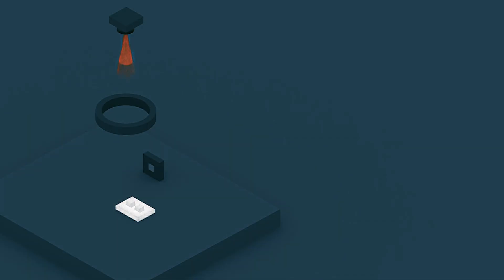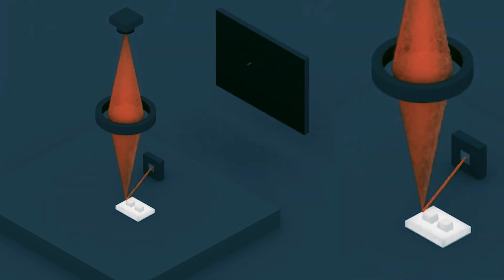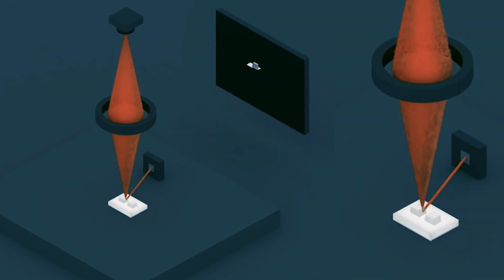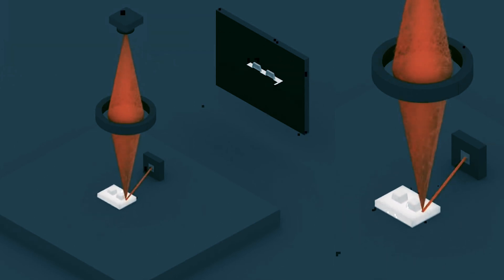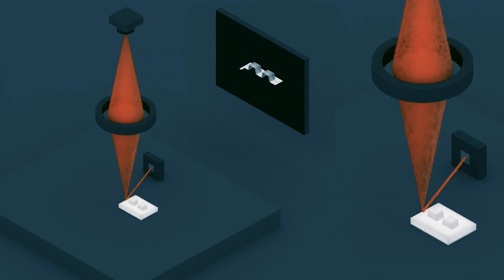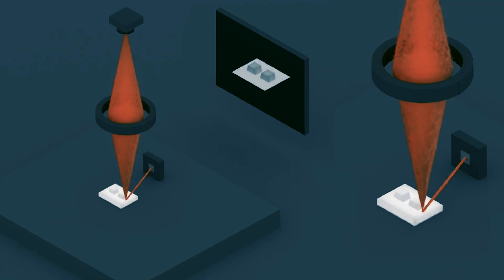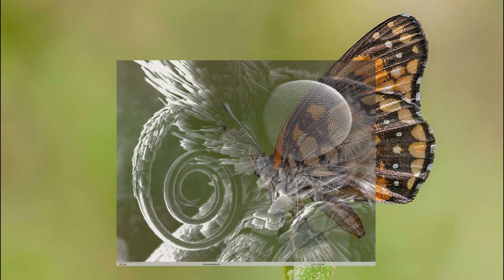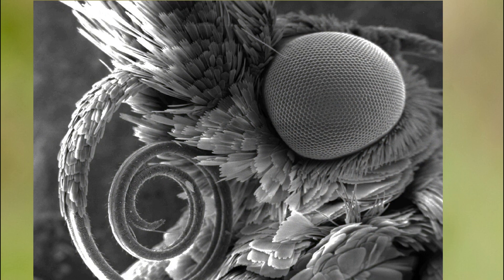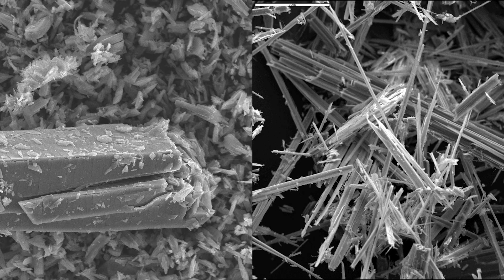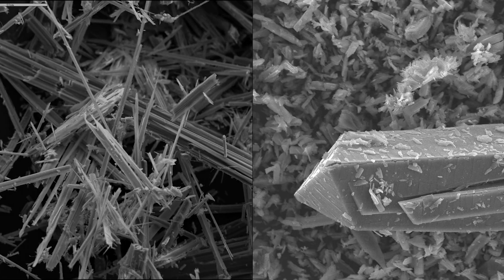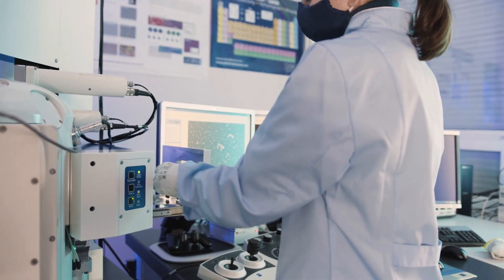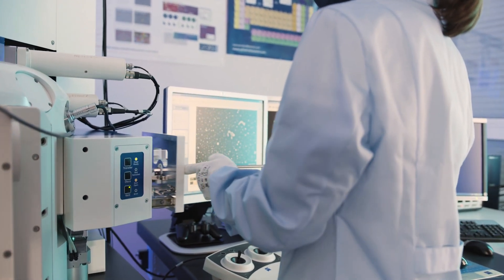First, let's talk about scanning electron microscopy, or SEM. SEM uses a focused beam of electrons to scan a sample surface. As these electrons interact with the atoms in the sample, they produce signals that are detected to form highly detailed images. SEM is ideal for studying surface morphology, especially in conductive materials and bulk samples. That's why it's widely used in fields like materials science and metallurgy.